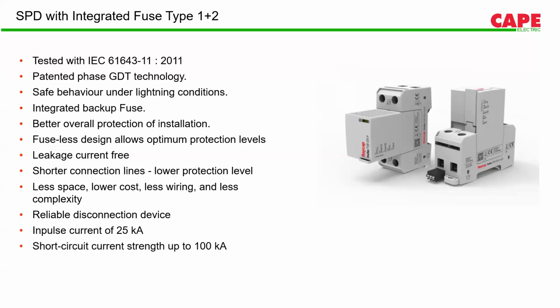Now with respect to SPDs, there are multiple current parameters. There is impulse current, there is nominal discharge current, there can be maximum discharge current, and there can be short circuit current rating, ISCCR. We'll discuss the impulse current also. First, the short circuit current rating: as per IEC 60364 part 5 section 53, it says that the short circuit current rating of an SPD shall not be lesser than the expected fault current at the connection point.